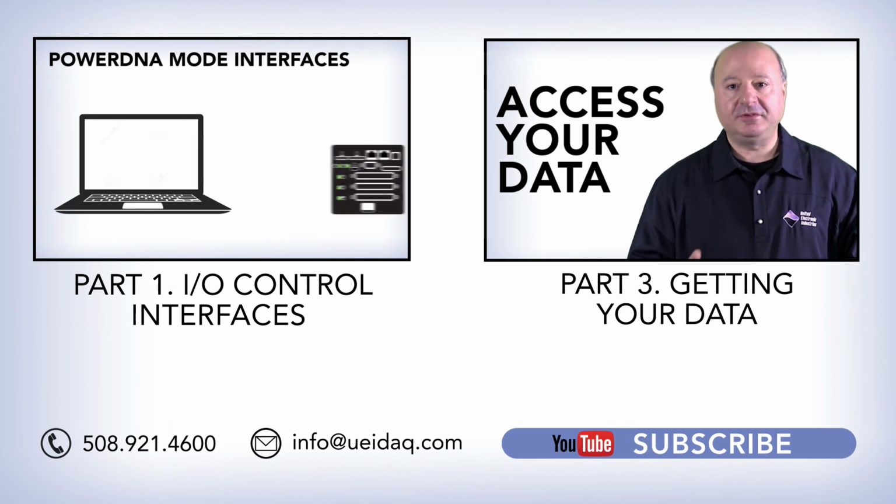In summary, if you need to collect data up to 100 Hz for your application, point-by-point mode would be most appropriate. If you need to get at the sensor's data quickly, possibly to make a decision, as in a control application or for some other reason, across an arbitrary number of I/O boards and a variable number of channels per I/O board, you would want to use DMAP or VMAP. And if you need a large amount of data about a signal with 100% packet integrity, ACB mode would be your best solution. Please see our other videos in the series.